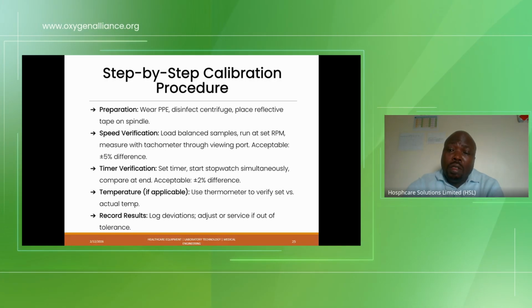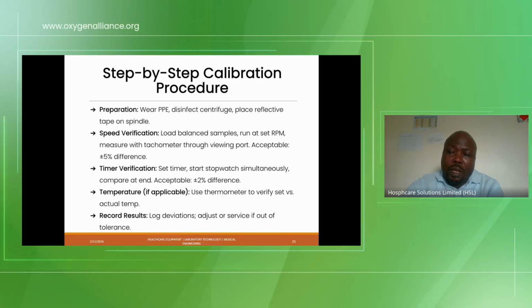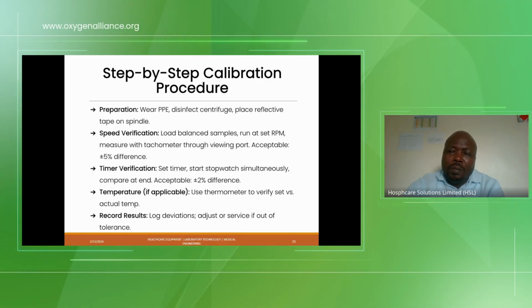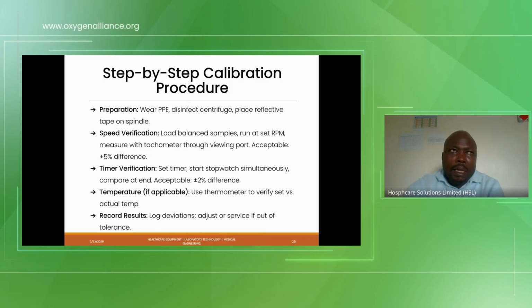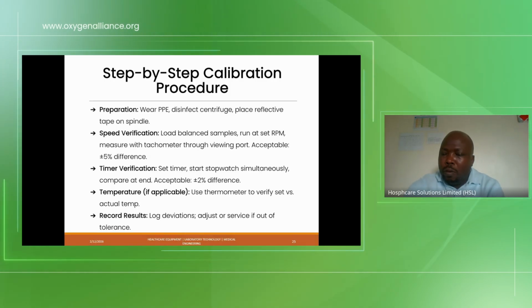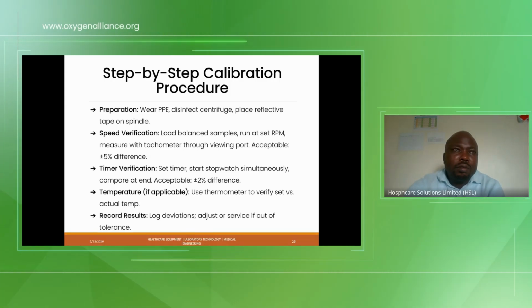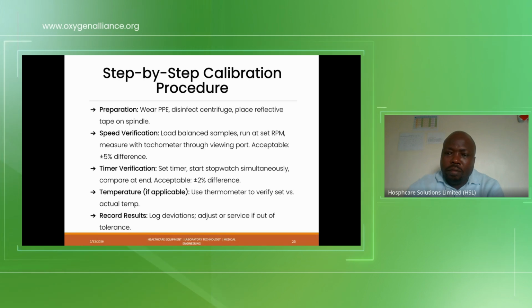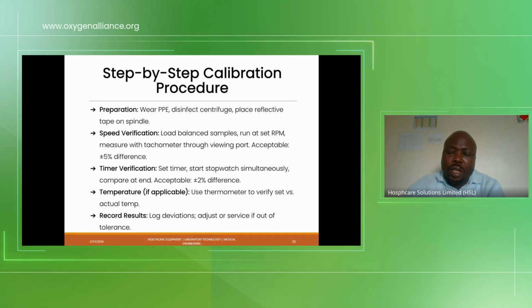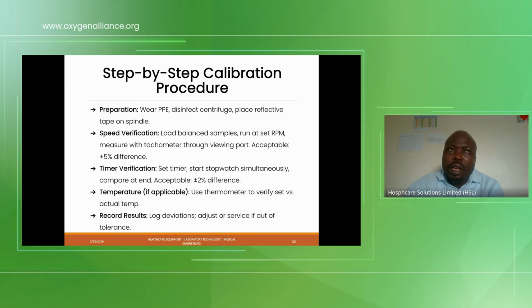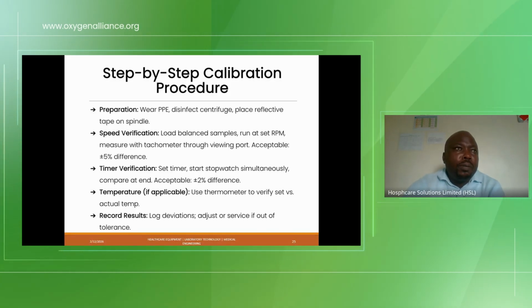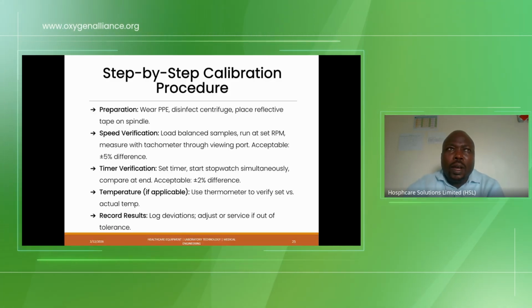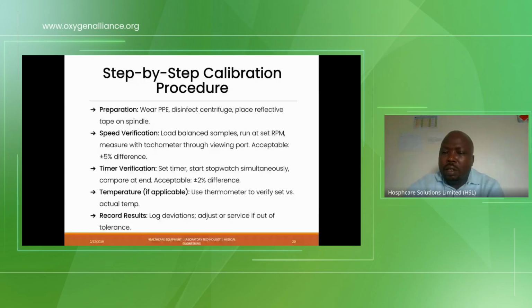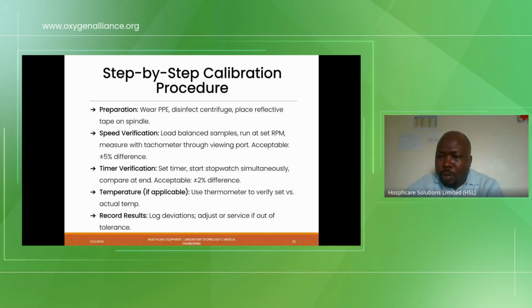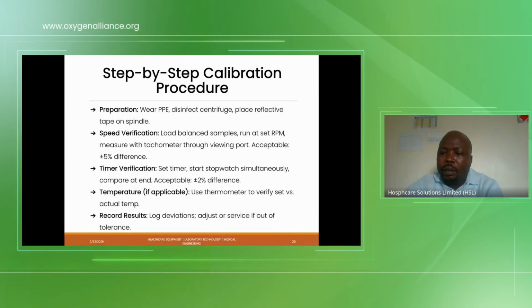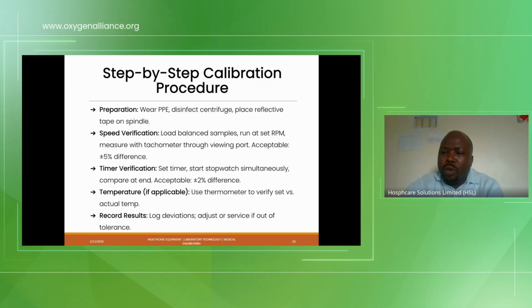Now, you calculate the errors in terms of percentage. If the percentage lies below minus or plus 5%, then your machine is still within normal working range. If it goes beyond 5%, then you will be required to adjust the speed from the user interface control panel. I think that is understood.